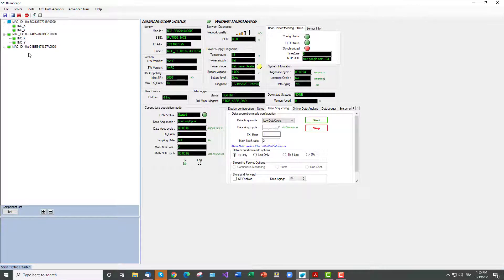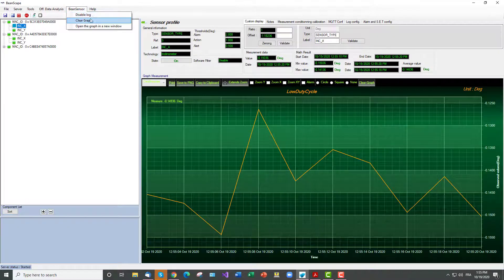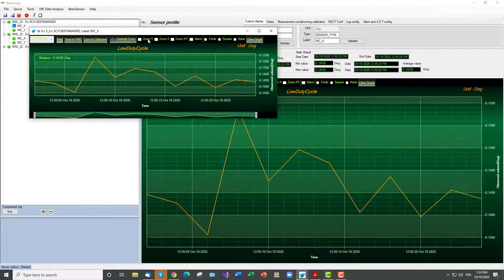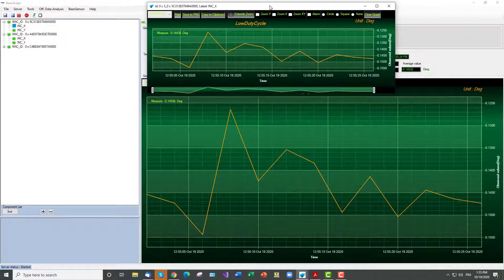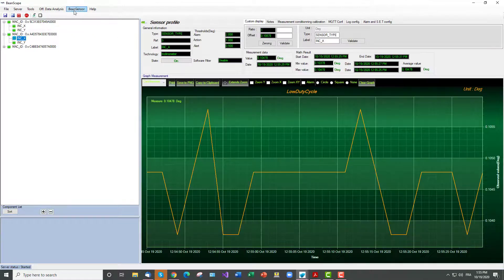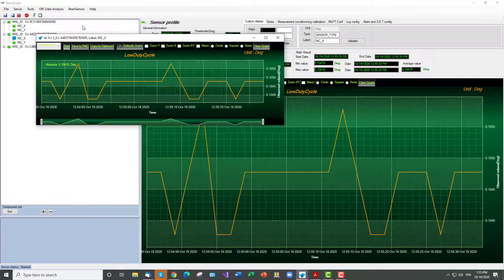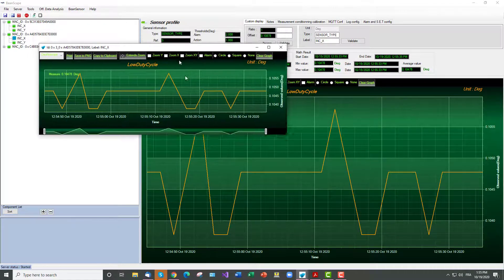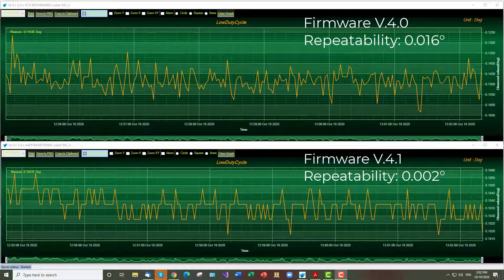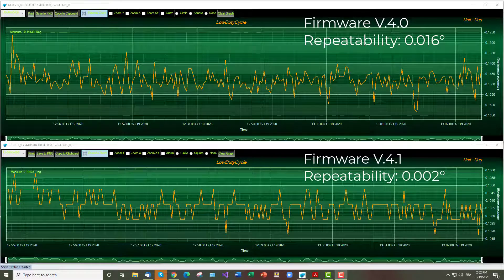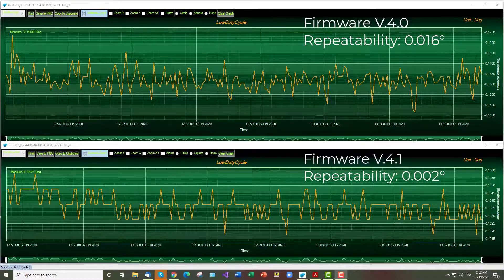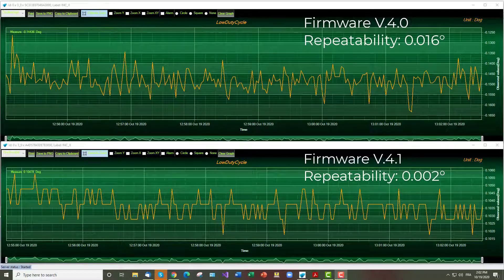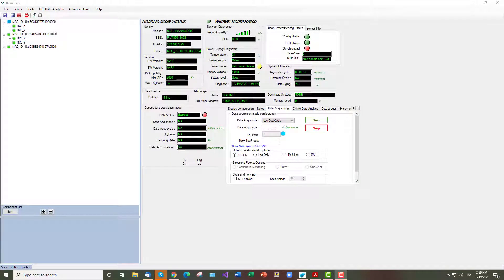Now we will open two different charts for each device. You can see that the repeatability was improved on the firmware version 4.1 and the peak to peak value is lower and much better than the old version. Now we will move on to the next section to evaluate the filters for the dynamic modes.